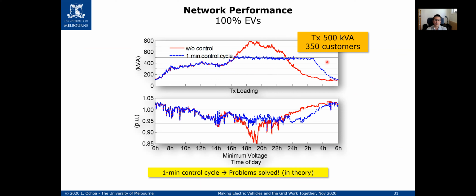But the idea with the simulation is to show that by following this algorithm we propose, you're able to avoid this massive peak in red, with no control, that goes beyond the 500 kVA rated capacity of the transformer, and instead keep it at 500 kVA. Naturally, the voltage doesn't go as low either, because the load is much less, but you still sometimes have problems with respect to the limit, shown by this line. But in general, you can solve the problems.